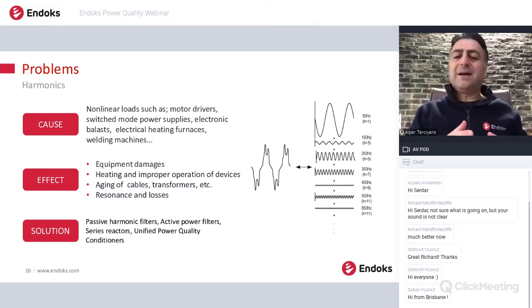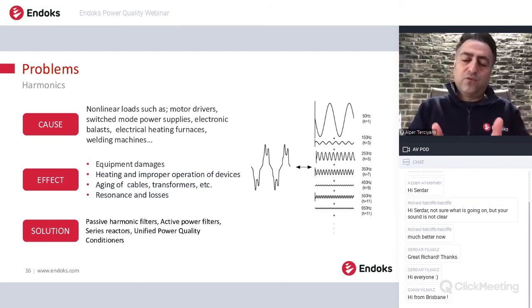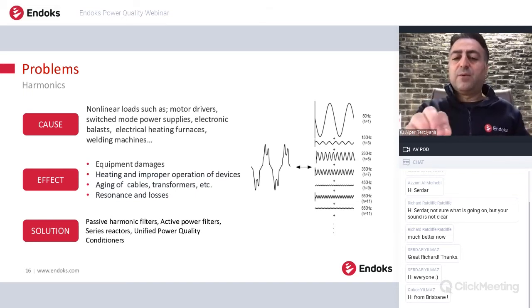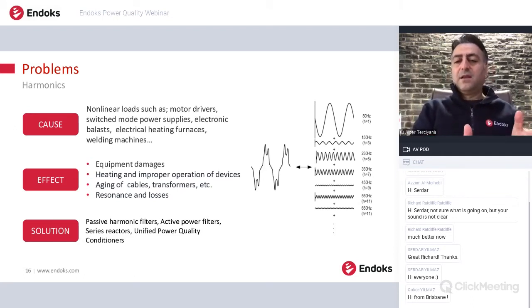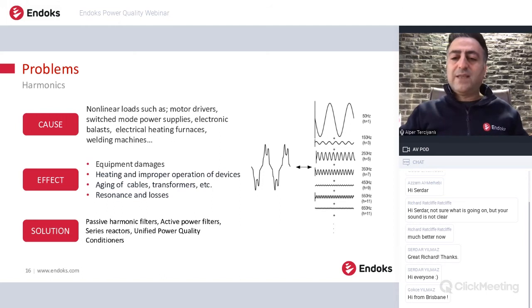Or we put some additional equipment into the system, and we can change the frequency of the resonance. So, for example, if the parallel resonance frequency of the system is 250 hertz, we can put in some additional reactors, and then we can shift this parallel resonance frequency down to, for example, 180 hertz. So even if we inject a fifth harmonic into the system, since the resonance frequency has shifted, there will be no risk. Of course, we need to study and find what the parallel resonance frequency of the system is and how we can solve it.